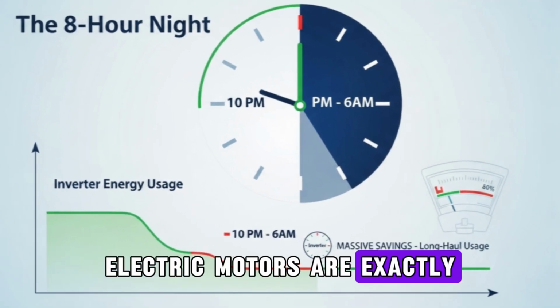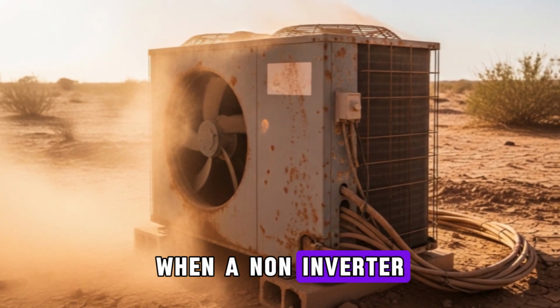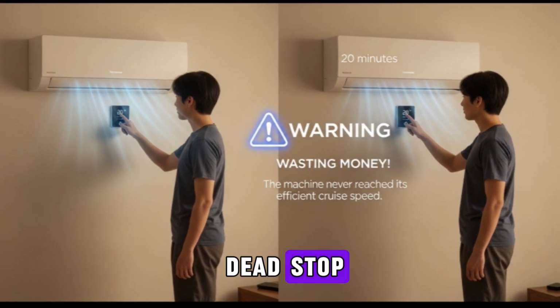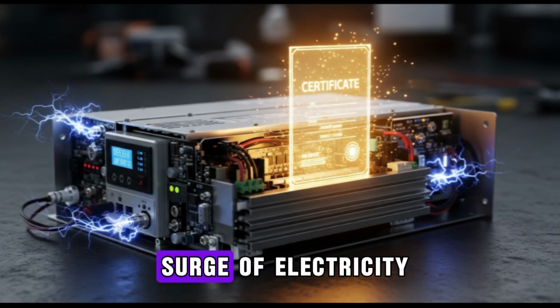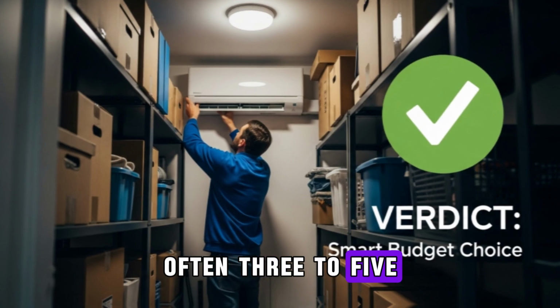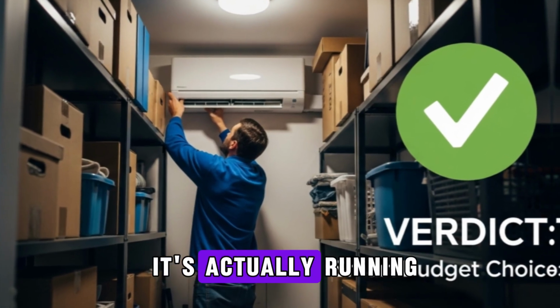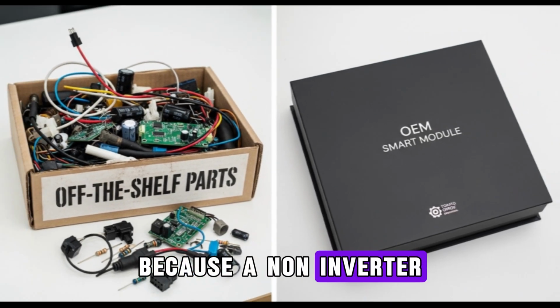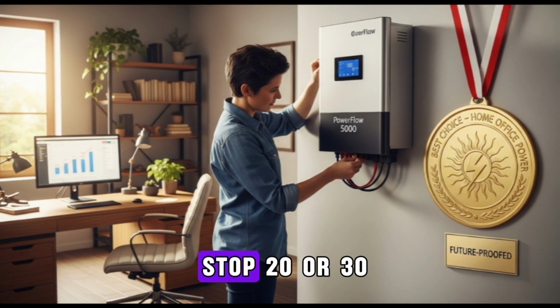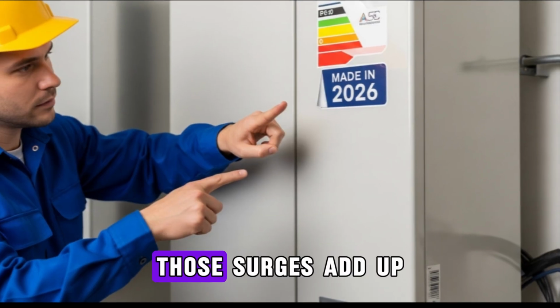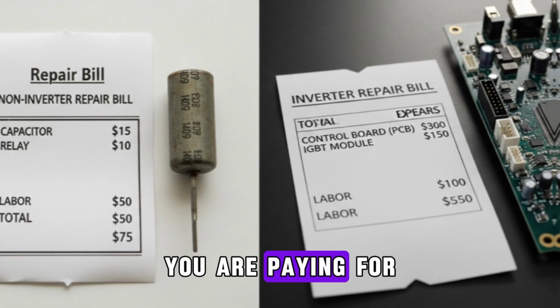Electric motors are exactly the same. When a non-inverter compressor starts from a dead stop, it requires a massive surge of electricity, often 3 to 5 times more current than it needs when it's actually running. Because a non-inverter AC might start and stop 20 or 30 times a day, those surges add up. You are paying for the effort of starting the motor over and over again.